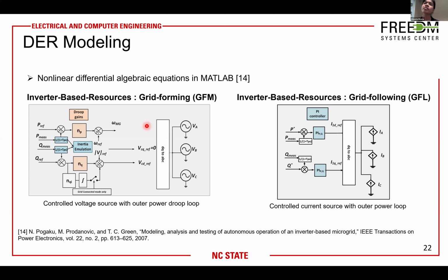So is there flexibility to include those things? You're saying different inverters with different dynamic responses? Yeah, because the topology also drives how quickly you can move power. When you say the topology is different, is the response of the outer power loop different, or is that response the same? Not every inverter responds in the same amount of time. We can have different inverter types integrated into this framework, there's no limitation. We just need an equation-based model of that particular topology integrated, and then we can compare the performance of different inverters. These are just examples we've currently used, but right now we're working to integrate synchronous generators, so there's no limitation on which type of DERs we can integrate.